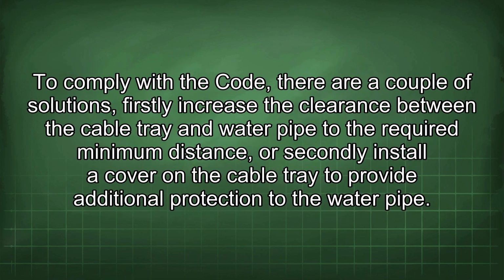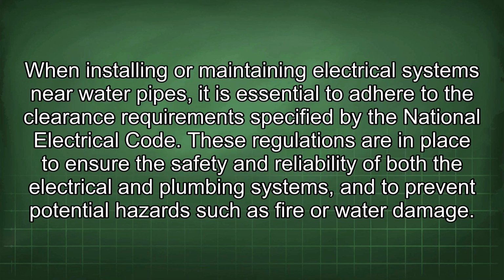To comply with the code, there are a couple of solutions. Firstly, increase the clearance between the cable tray and water pipe to the required minimum distance, or secondly, install a cover on the cable tray to provide additional protection to the water pipe. When installing or maintaining electrical systems near water pipes, it is essential to adhere to the clearance requirements specified by the National Electrical Code. These regulations are in place to ensure the safety and reliability of both the electrical and plumbing systems, and to prevent potential hazards such as fire or water damage.